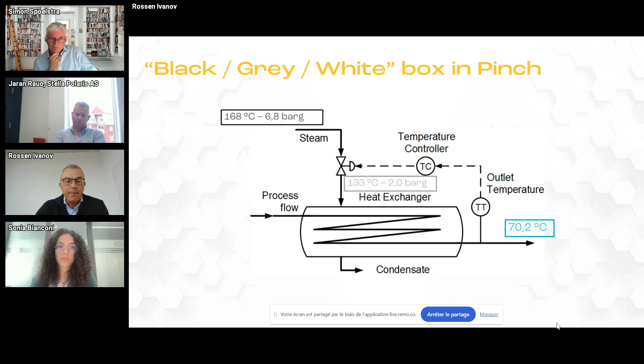And amazingly, the process engineer today starts to be very open-minded once the consequences of these high temperature lifts are understood. Minimizing the temperature lift really allows us to decrease both the capex and the opex on the heat recovery side. Of course, the heat exchangers need to be bigger. We need more heat exchange surface with hot water than we need with steam, and that's the kind of trade-off which is designed every day.